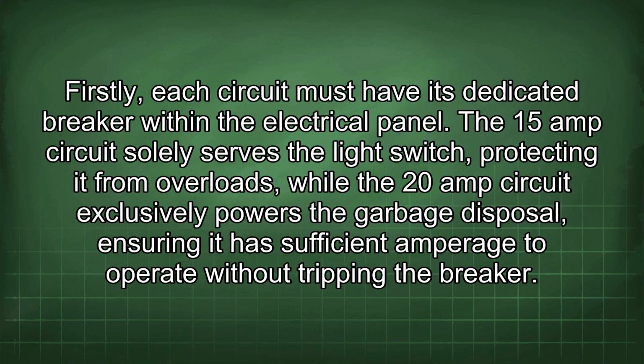Firstly, each circuit must have its dedicated breaker within the electrical panel. The 15 amp circuit solely serves the light switch, protecting it from overloads, while the 20 amp circuit exclusively powers the garbage disposal, ensuring it has sufficient amperage to operate without tripping the breaker.